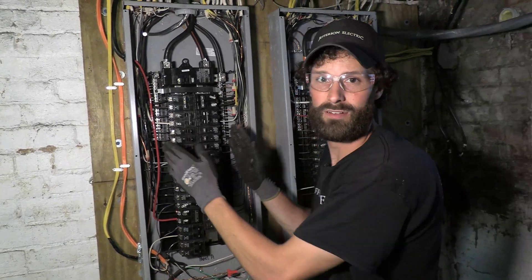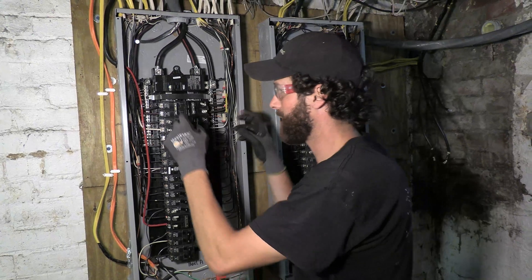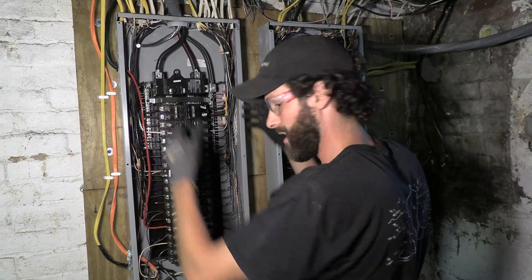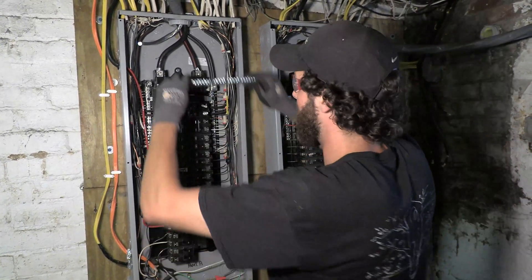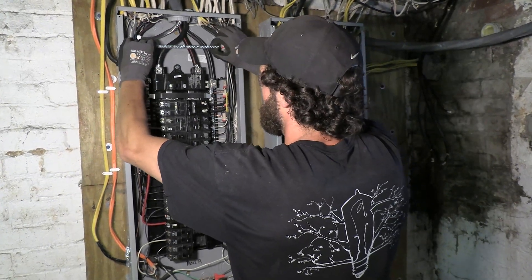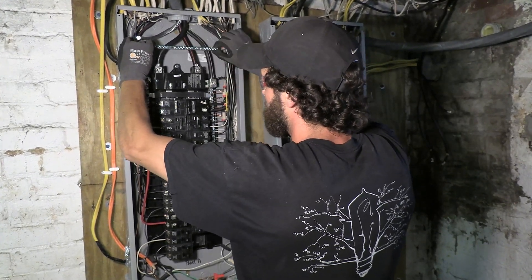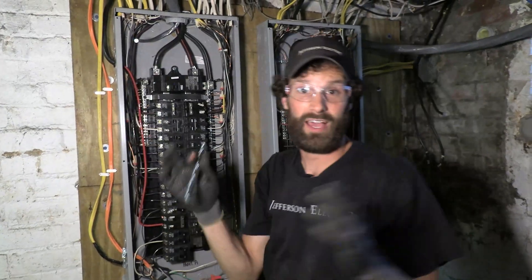I'm going to leave, because those are insulated bars, I'm going to leave the neutrals there, and I'm going to lift all the grounds up, and I'm going to install them at the top behind these conductors on this new terminal bar right here. So let me show you how that's done.